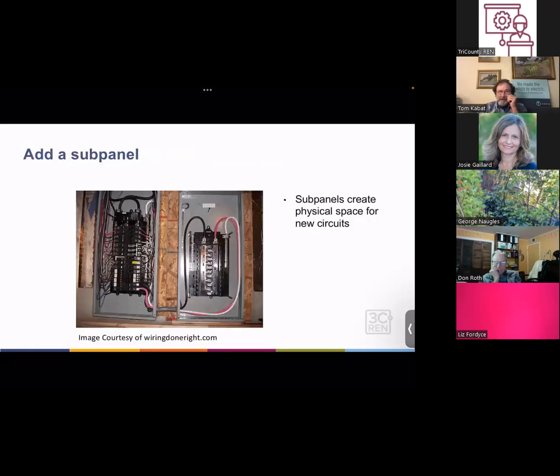Next. And then the big approach to it is just putting in a sub panel. In this one, the sub panel is located right next to the main panel. You see it on the right side. But often it'll make sense to not locate it right there, but to move it close to where you're adding the new circuit. So you can run one big feeder wire. That's what they call the wire that powers a sub panel. One big feeder wire over to the sub panel, and then having shorter runs out of the sub panel to meet the devices. So next.